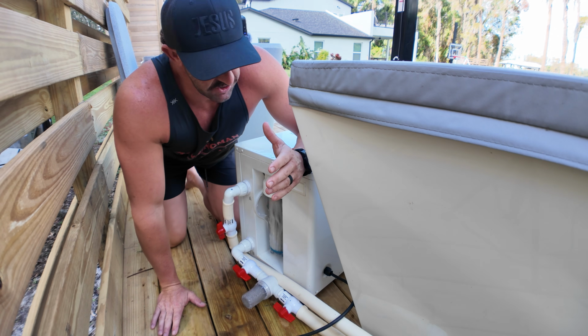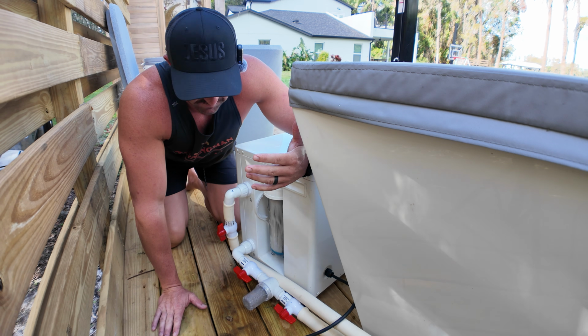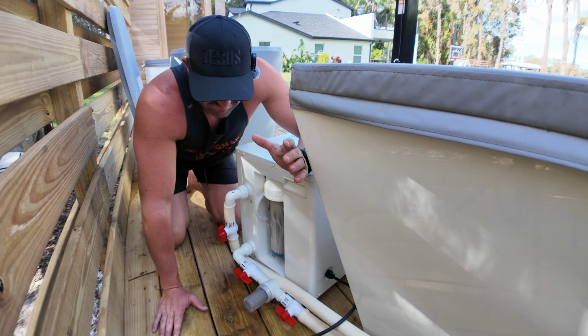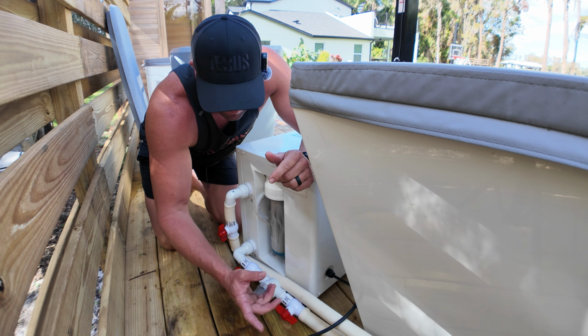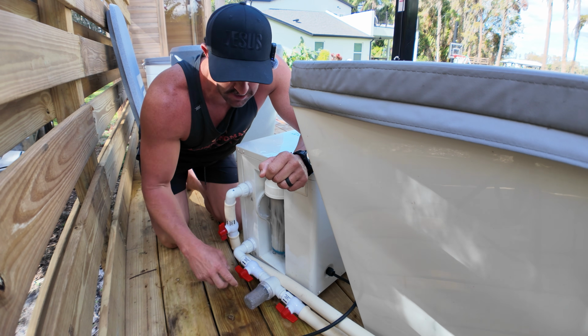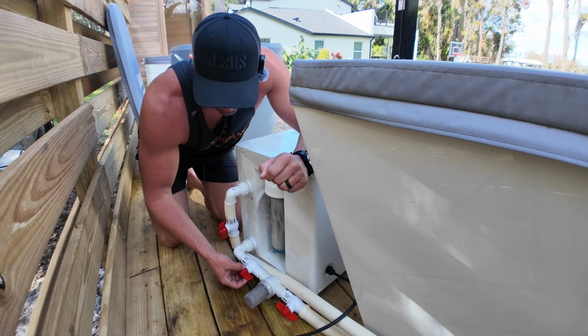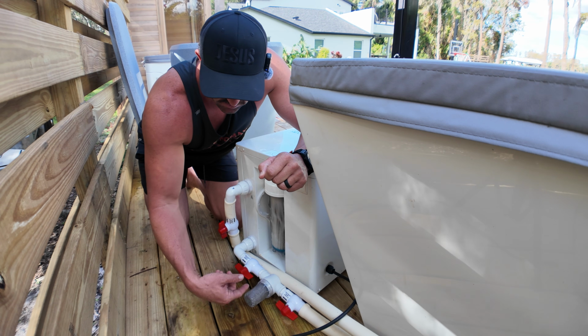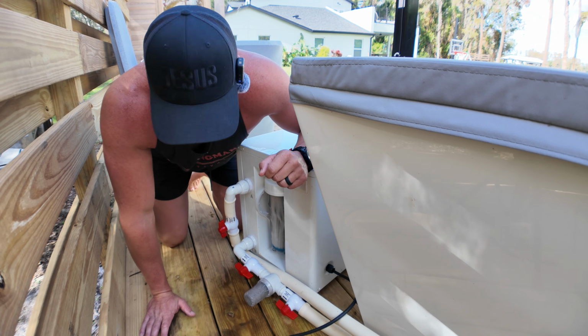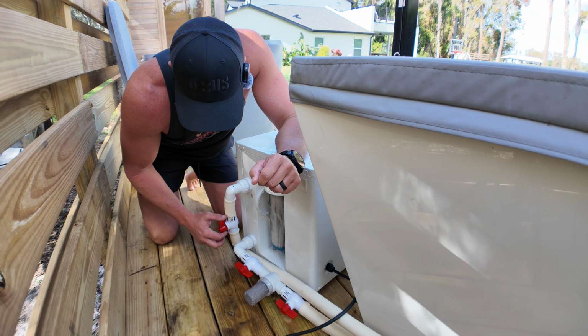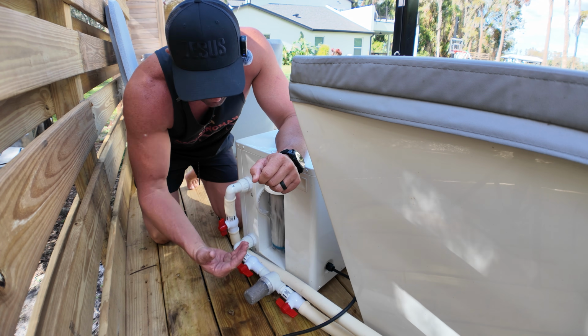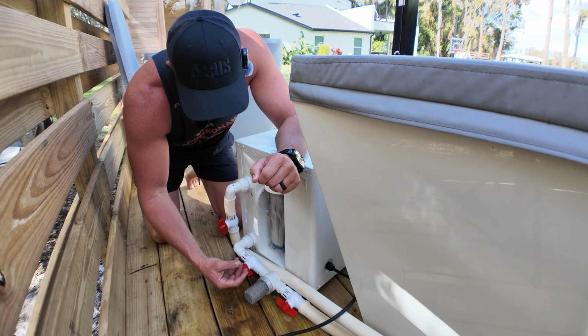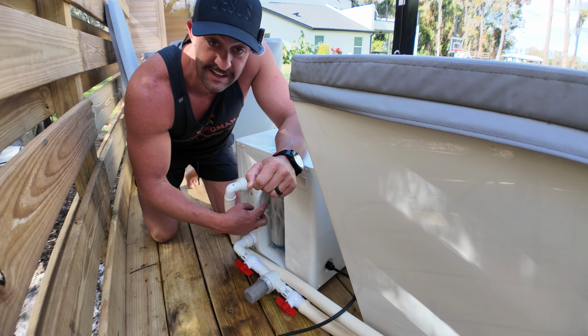Quickly, let's talk about the standard chiller. I have this on, I'm not gonna change the filter. I just replaced the filter on this, but it's very similar. You have a pre-filter over here. You can unplug this chiller. Once you unplug it, you can close both of these, which you can then rinse out and clean out your pre-filter, which is great. It does have a shut off over here, so that will prevent a lot of water from coming out of this when you open this, but this canister can get a little tight.